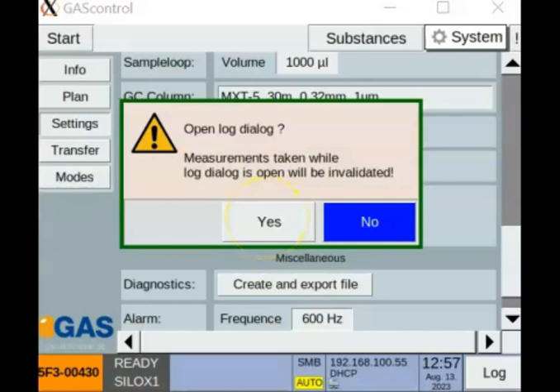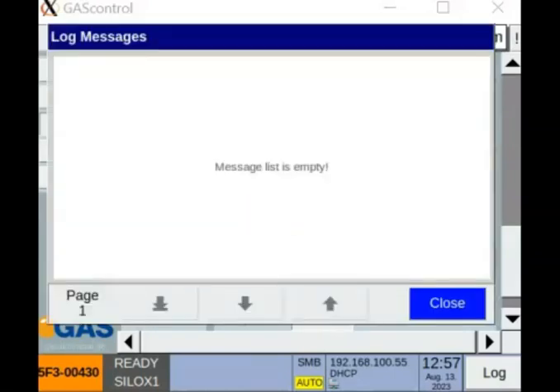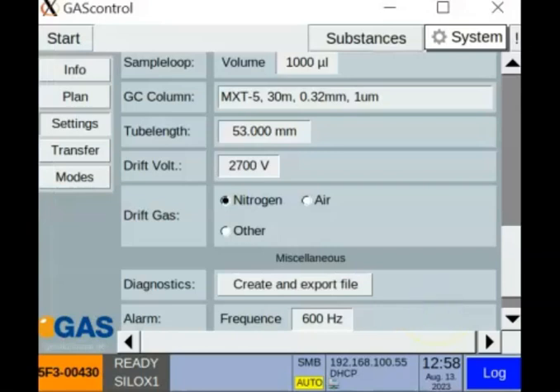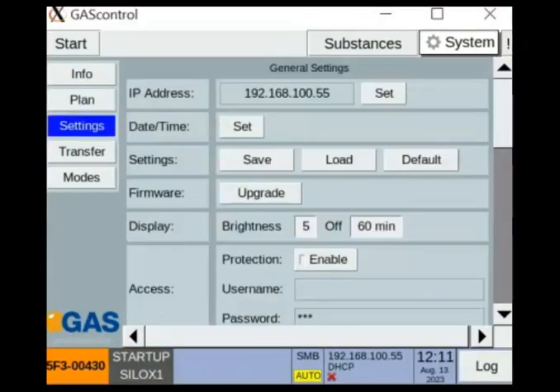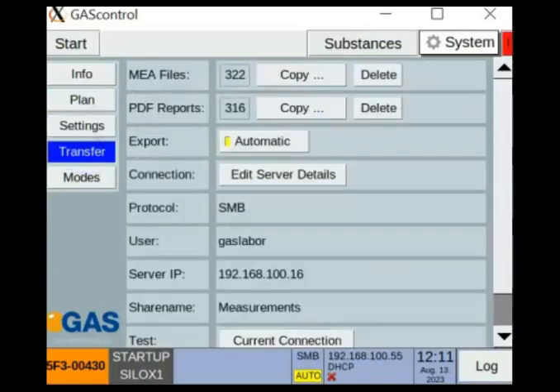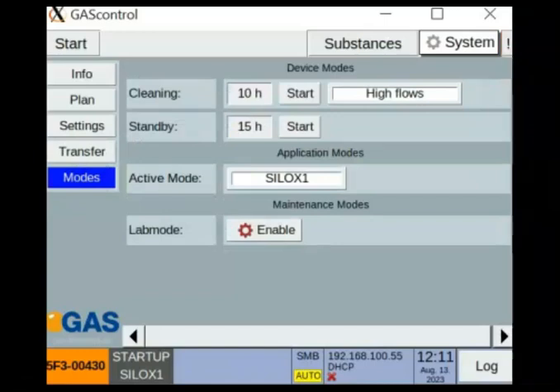No measurements can be taken, and there is no message at the moment, no error of the system has occurred. We have the transfer settings to communicate with a server to exchange the measurement files, and there are different measurement modes of the instrument. We can select the measurement type, as well as we can send the instrument to a cleaning or to a standby. If we use the standby, we can save the gas.